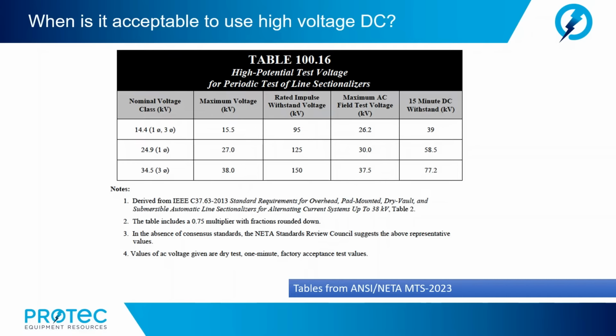All right, let's move on, and now let's take a look at table 100.16 of the NETA guides. High potential test voltage for periodic tests of line sectionalizers. Now again, this table we see in the notes was derived from IEEE C37.63, standard requirements for overhead, pad-mounted, dry vault, and submersible automatic line sectionalizers for alternating current systems up to 38 kV. Now, here we do see that the values of AC voltage given are dry tests for 1 minute duration, and we see that DC is also called out as an option, but the test extends out to 15 minutes when DC is being used.